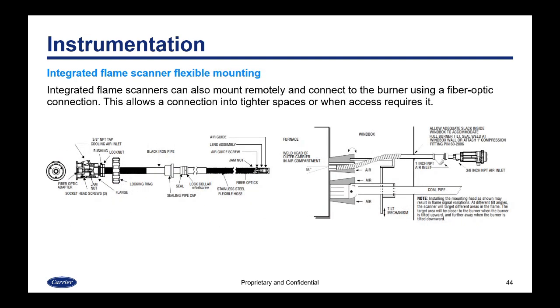Integrated flame scanners can also mount remotely and connect to the burner using a fiber optic connection. This allows a connection into tighter spaces or when access requires it. With the fiber optic cable, because of access you may need to locate the scanner a little further away, and the fiber optic cable allows you to get the angle you need to see what you need to see.